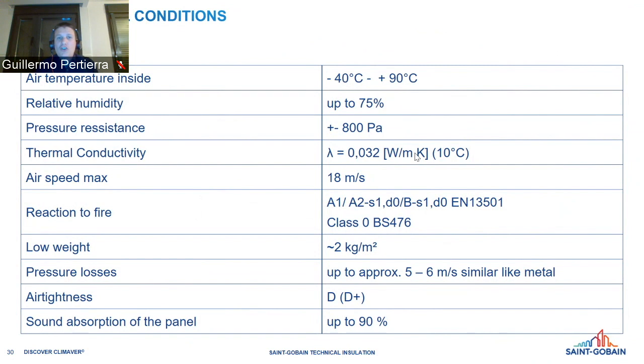Pressure losses are equal at the typical air speed of the ducting, typically between 4 and 8 meters per second, and at this speed the pressure losses are similar to traditional metal ducting. The air tightness of the system is excellent, better than the best class that exists today, it's D+, better than class D which is the best in the standards. Sound absorption is up to 90%.